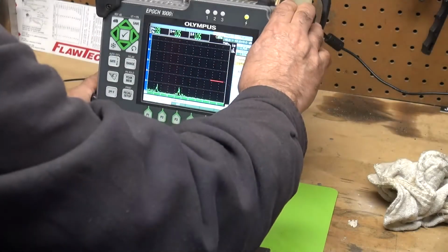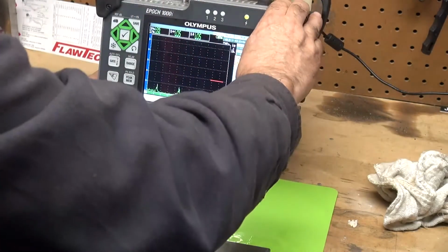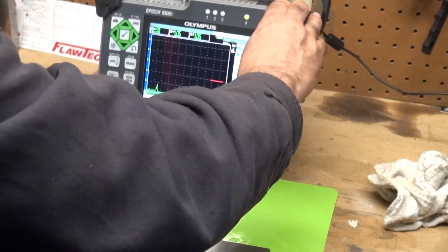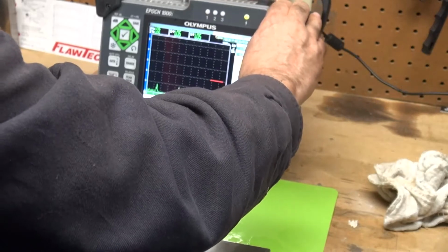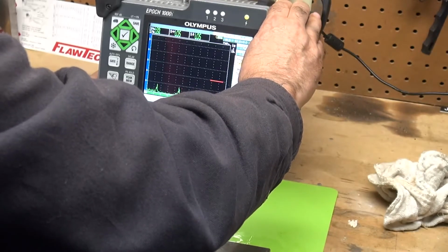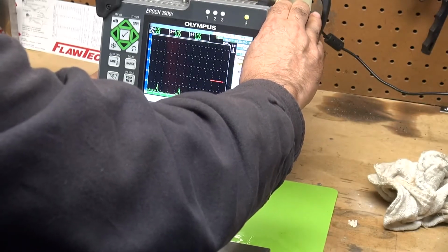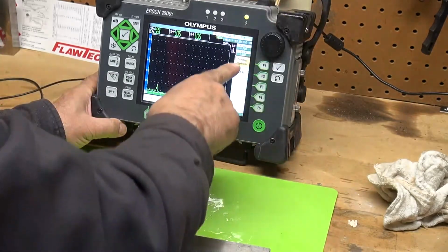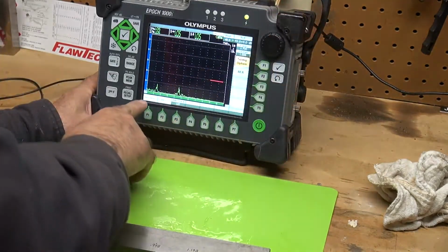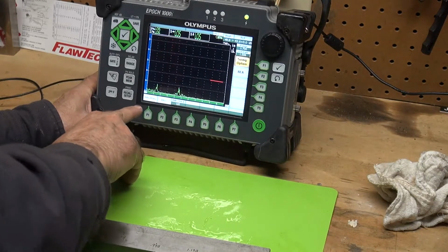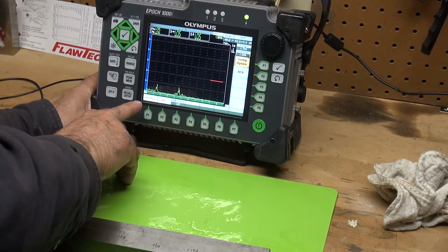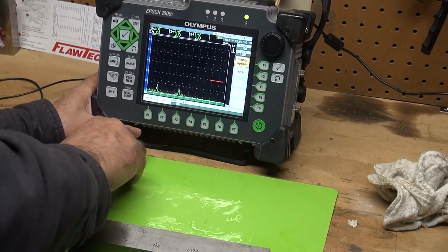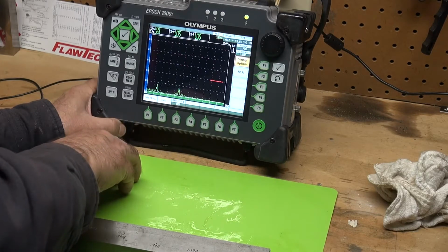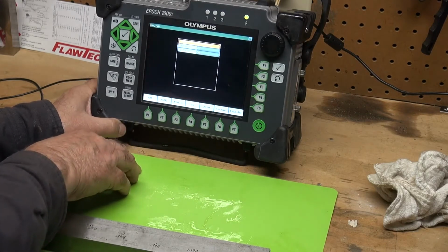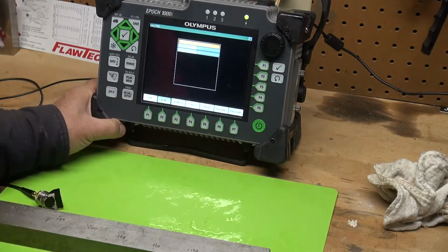So what we do, of course, we calibrate our machine, and then in our options, we go to screen 4 of 5, sizing options. Press the sizing options. Down here it says DAC for distance amplitude correction, DAC or TVG, time varied gain. Press that. I'm going to press ASME, and then I'm going to hit the return key.